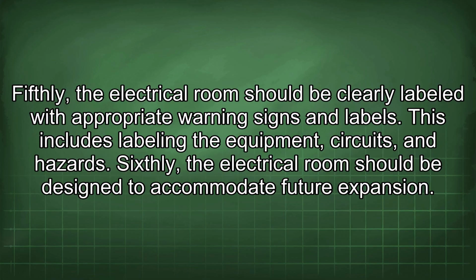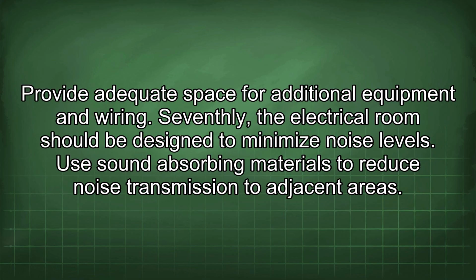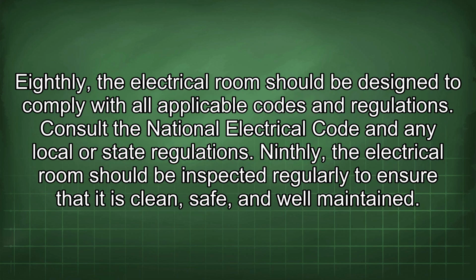Sixthly, the electrical room should be designed to accommodate future expansion. Provide adequate space for additional equipment and wiring. Seventhly, the electrical room should be designed to minimize noise levels. Use sound-absorbing materials to reduce noise transmission to adjacent areas. Eighthly, the electrical room should be designed to comply with all applicable codes and regulations. Consult the National Electrical Code and any local or state regulations.